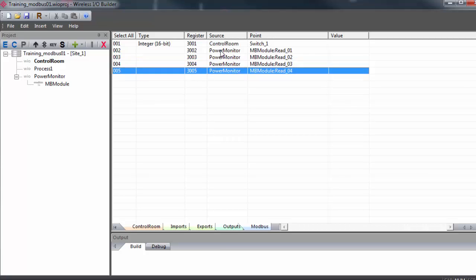These are the registers in the gateway's Modbus holding table where the data from our Modbus slave will be placed. The values generated in the slave device will be read into the power monitor gateway and then propagate to these registers in this gateway, which can then be pulled by our PLC, acting as a Modbus master on this end.